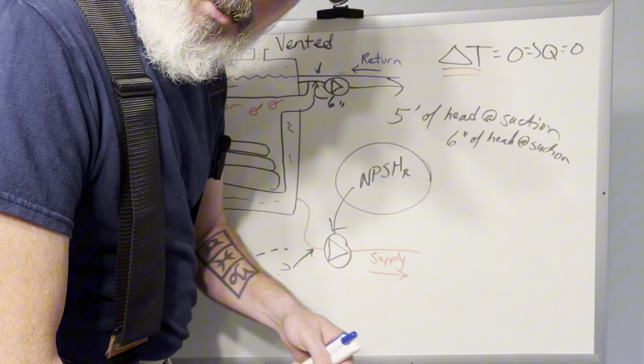There is something those pump manufacturers will tell you, called net positive suction head required. That is a requirement, and depending on your situation, if you pull from up here, you're probably not going to have that. You can get pump cavitation and destroy the pump. But just some stuff to think about.